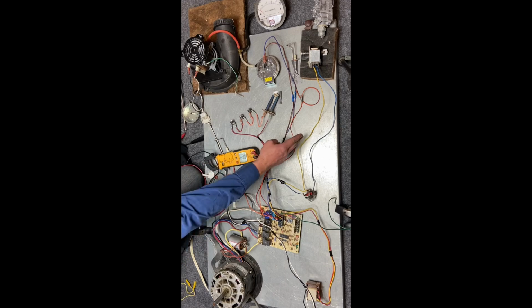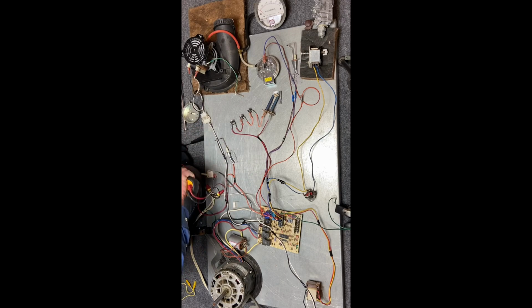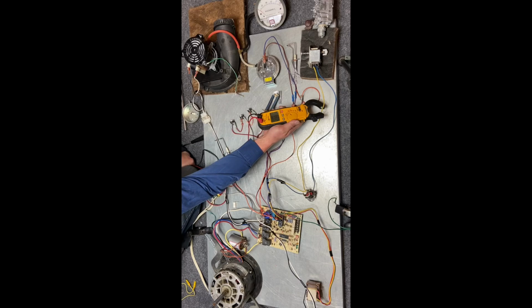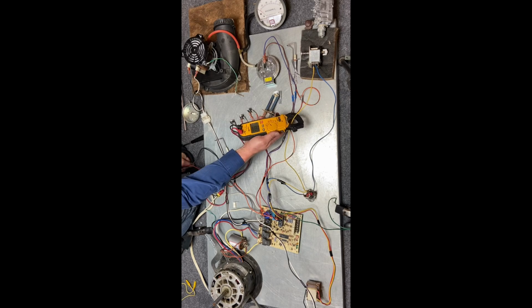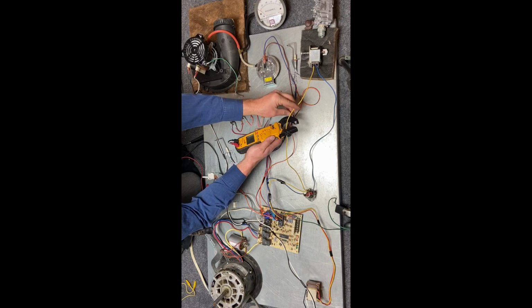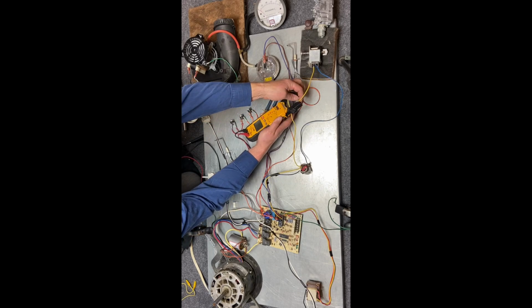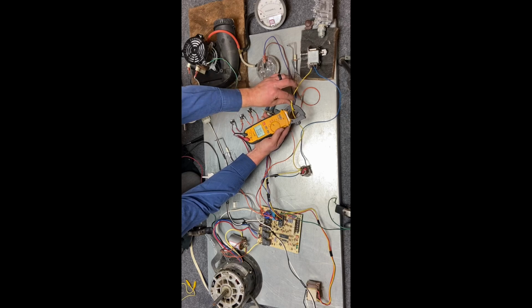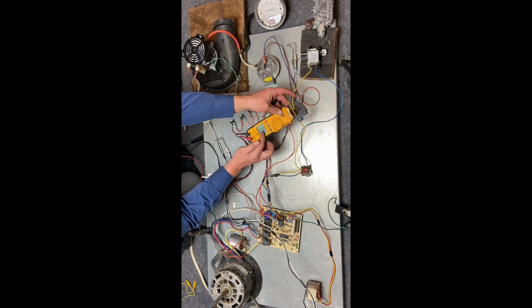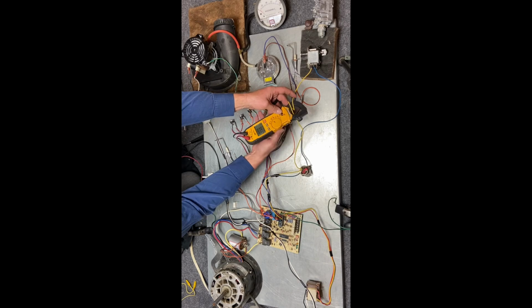We can also check the amperage to our combination gas valve, but because it is low voltage, it doesn't give us a very accurate reading because it's a very small flow of amperage. So what we can actually do is take this wire and wrap it around the meter, and that doubles the magnetic field. So whatever number I get, I divide that by 2, and that gives me a very accurate reading of the amps. One last thing before we get done is we want to see this flame sensor.